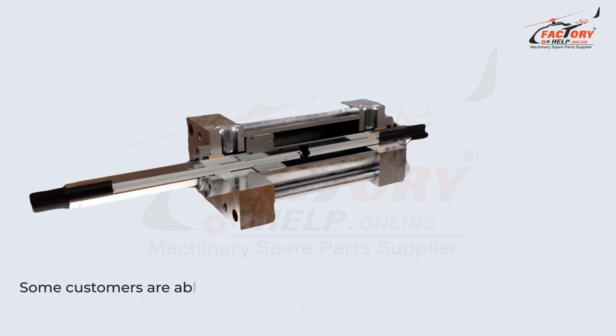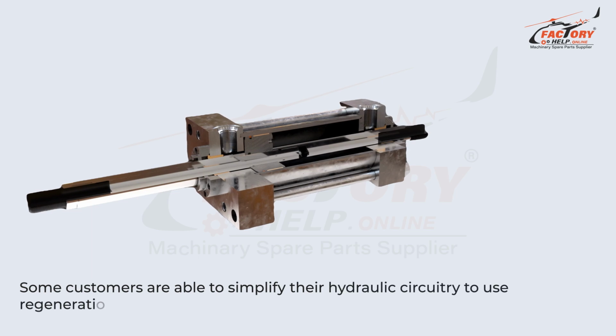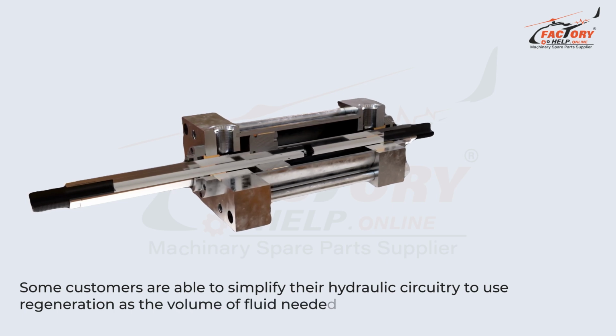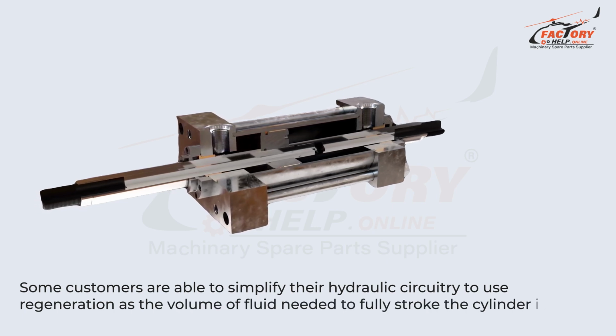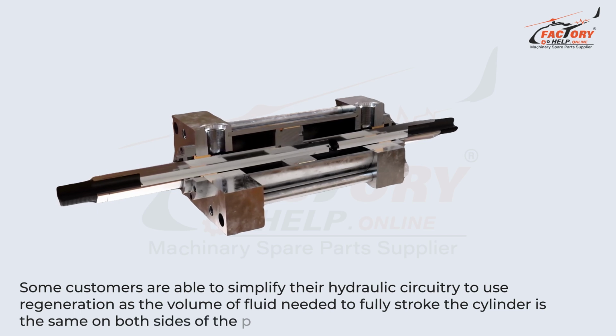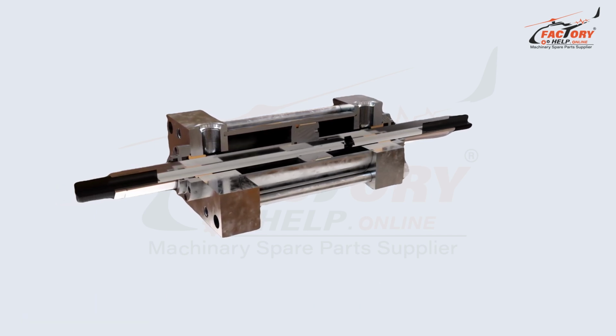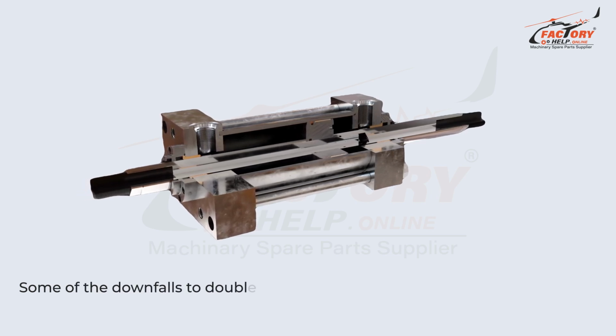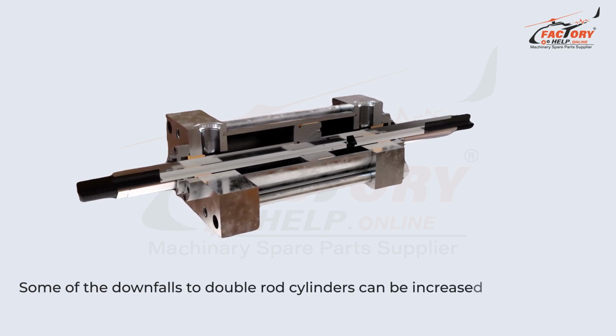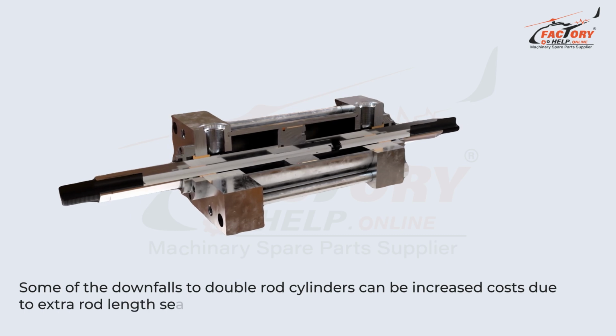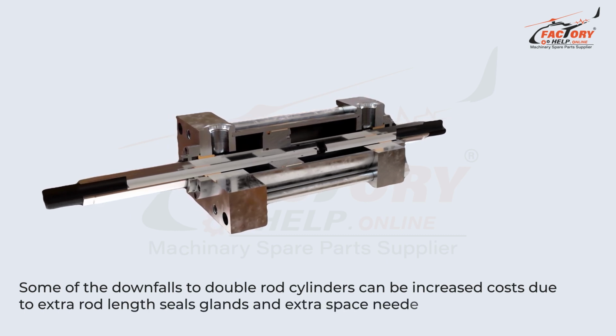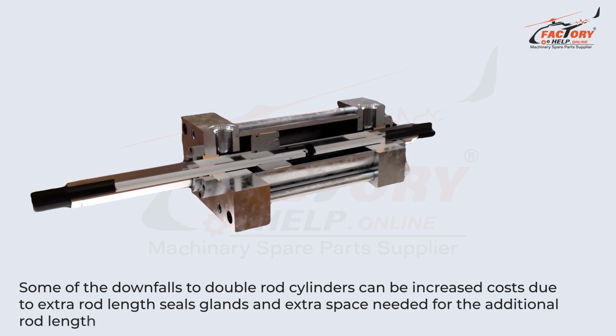Some customers are able to simplify their hydraulic circuitry to use regeneration, as the volume of fluid needed to fully stroke the cylinder is the same on both sides of the piston. Some of the downfalls to double rod cylinders can be increased costs due to extra rod length, seals, glands, and extra space needed for the additional rod length.